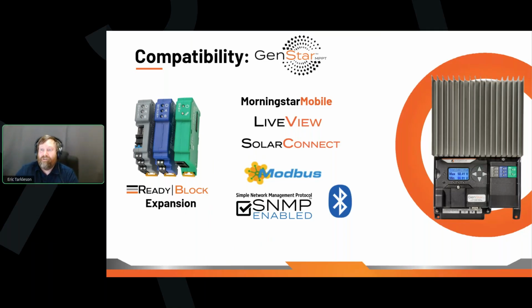It's also worth mentioning that Modbus is served through the Ethernet IP port on the GenStar. So any data that you see in SolarConnect, there is a Modbus address for that you can get at it for other site monitoring, connecting to PLCs, SCADA systems, things like that. And the GenStar and the ReadyBlock also have SNMP enabled. So if you're online, that's another access to get your data off of your local site onto the broader internet. And if I didn't say it already, also Bluetooth. The GenStar has Bluetooth built in, and that's how you use it to connect to your app.